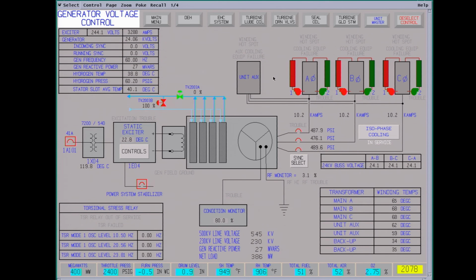The unit auxiliary, this is the power the plant is using. It's taken off before the main transformers. Comes in here 24,000 volts, stepped down to 7.2 kV. So all the motors in the plant are 7.2 kV, or 7,200 volts. Get your main transformer winding temperatures.